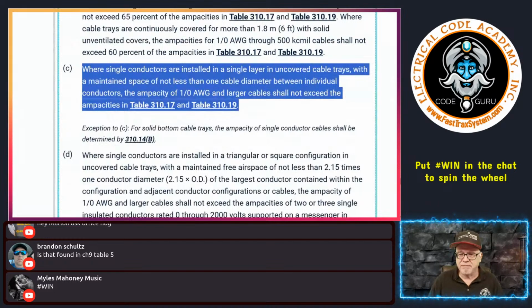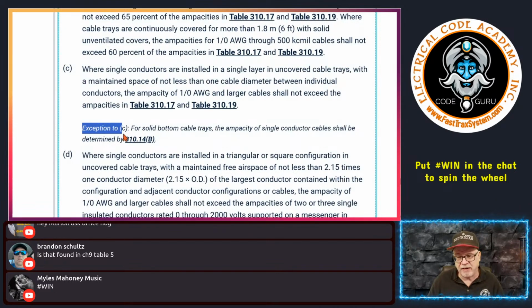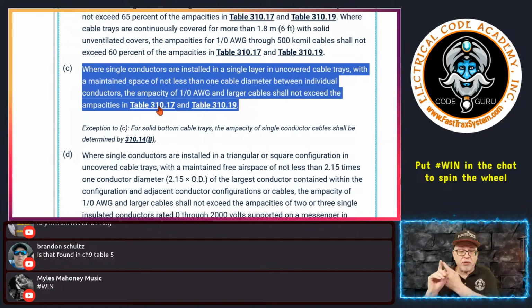But here's the caveat. What if it's a solid bottom cable tray? It's not a ventilated bottom or a rung style. What if it's not? Uh-oh. Well, then you got this right here. It says, uh-oh. See all this nifty that lets you just use the pure amp. Remember, you're still going to be limited to terminals. So don't ever forget that. This doesn't give you carte blanche to use the 90-degree rated ampacities in those tables if the terminations are only rated 75. Y'all know that, right? I don't need to tell you that.